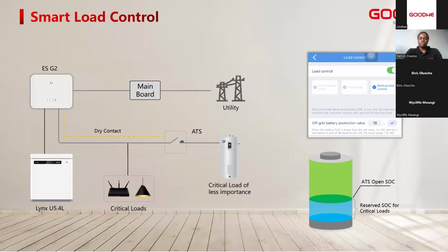And you have the chance of controlling these loads in 3 modes. Either you can switch them on manually, or you can time the operation of such big loads so that you limit the times in which these loads draw power from the inverter, the battery, or the grid itself. Additionally, you can control these large consuming loads by checking the battery state of charge. In this sense, you can reserve some power on your battery for your most critical loads that you don't want any power interruptions to.